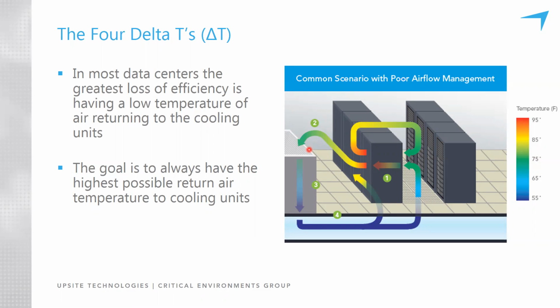And that's obviously because conditioned air, extra bypass airflow from somewhere, either coming out of unsealed cable openings as indicated right there, or extra supply tiles somewhere else in the room flowing over the tops of the cabinets, extra conditioned air has mixed in and reduced those air temperatures.